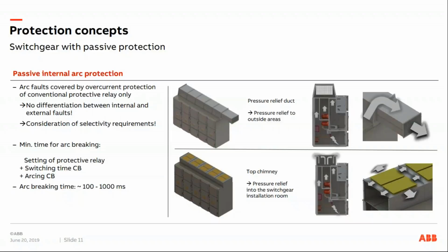However, what you can see here is that for a passive arc fault protection with gas ducts, and the fault happening here in, for instance, the cable compartment, the hot gases are going up to the top to the pressure relief duct, and then the gas duct takes away the hot gases outside the switchgear room. Another option is the top chimney, where you have, again, for instance, an arc fault happening in the cable compartment. Hot gases are directed to the upper part of the panel, and the top chimney then reduces the pressure and cools down the hot gases.